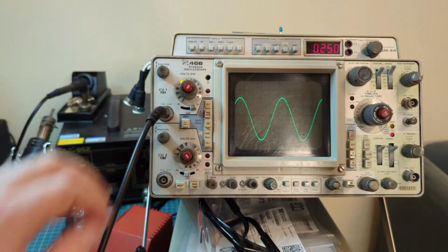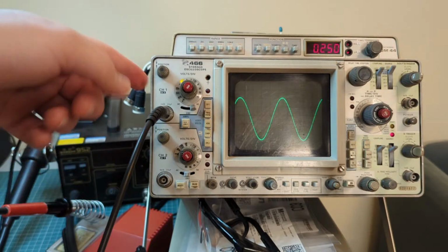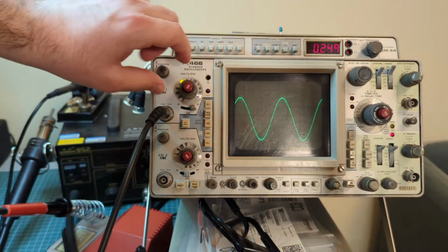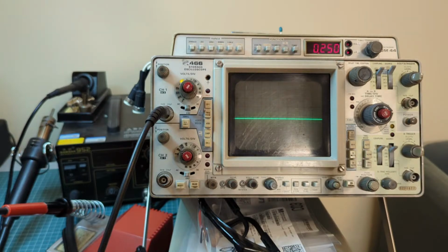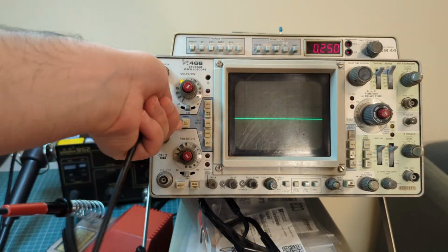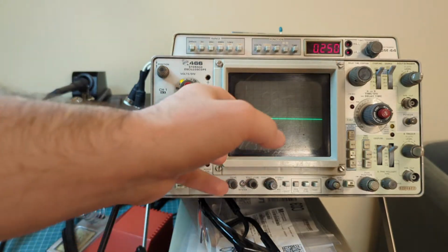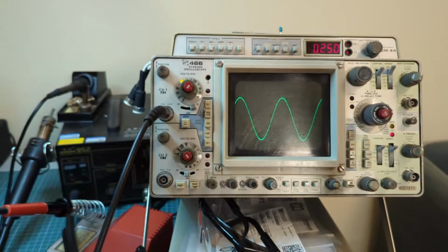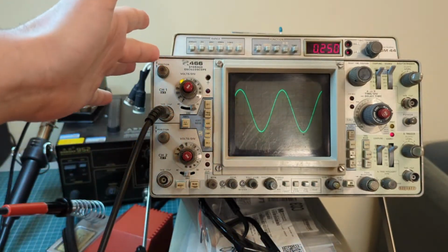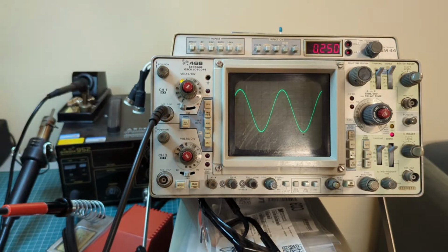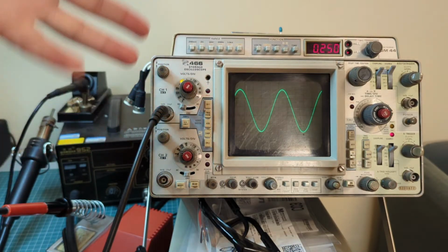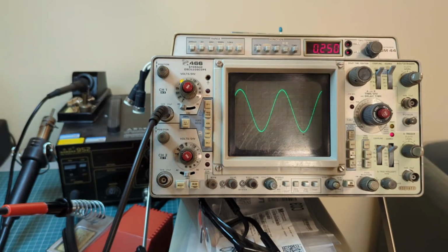So what the vertical can do is, first of all, let's look at the input coupling. This is really important. A scope like this has 3 modes for input coupling. It has ground, which means that the signal is basically disconnected from the vertical section. Then we have DC, which means that the signal is directly connected to the vertical section. And then we have AC coupling, which means that the input signal is connected to the vertical section using a blocking capacitor that basically removes the DC component of the signal.